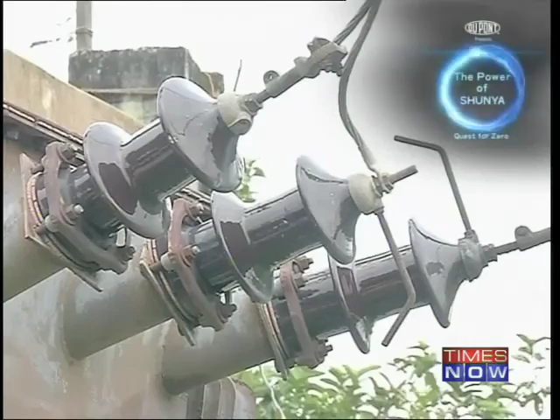A present problem on the rural feeder is that the transformer gets burnt quite often, and once it's burnt, replacement takes time. This is because the supply is not segregated; sometimes due to general consumers on the agriculture feeder we are getting low voltage and are not able to run the pump set. Sometimes general villagers complain that because you have put the agriculture pump set, we are not getting proper voltage for our supply.